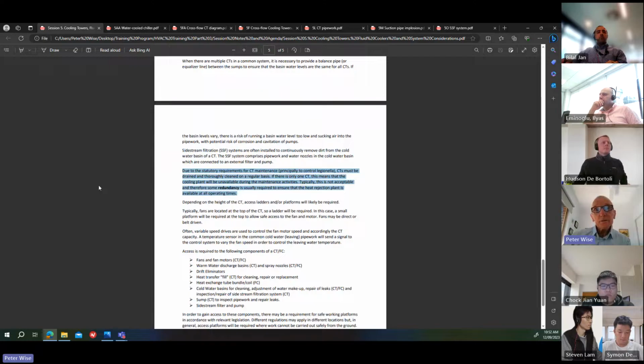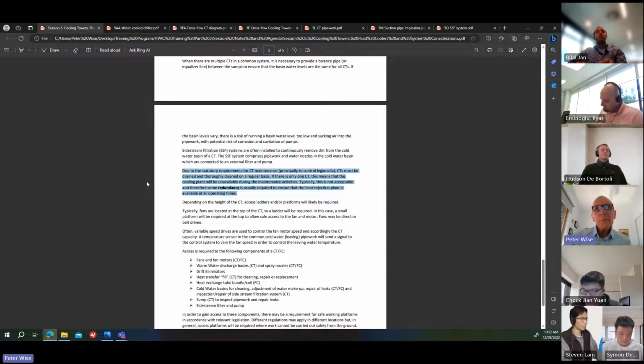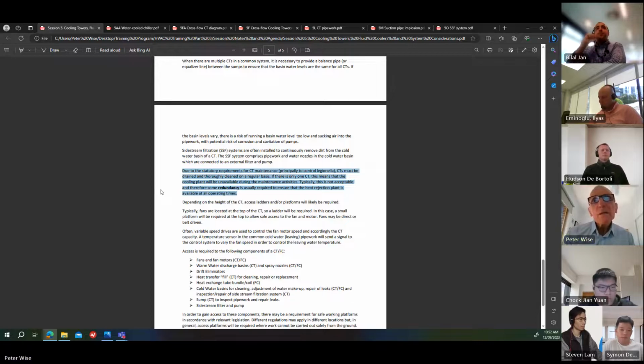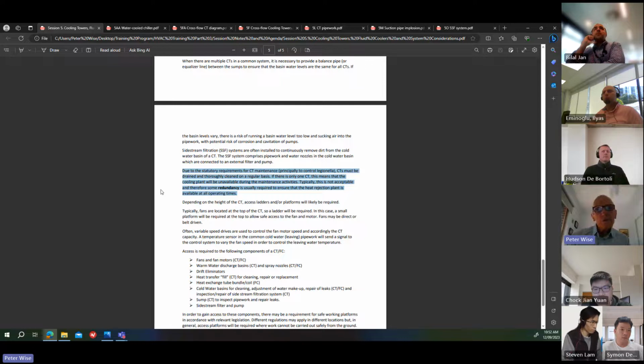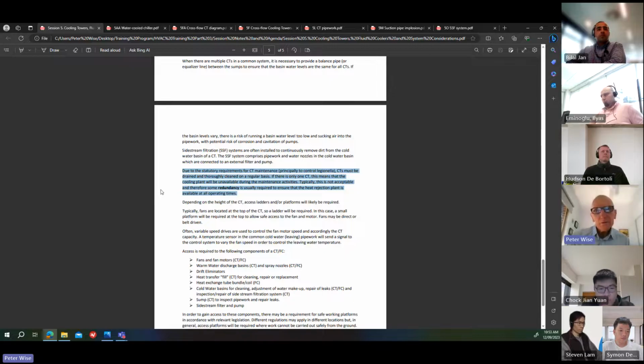Now, there are statutory requirements for cooling tower maintenance. As I mentioned before, a cooling tower has to be registered with the local council, so the council knows it's there and it's got to be looked after. The idea is principally to control Legionella, because nobody wants Legionnaires' disease to occur in their local area. Part of the requirements are that the cooling towers must be drained and thoroughly cleaned on a regular basis. If there's only one cooling tower, this means that the cooling plant will be unavailable during the maintenance activities. Typically, this is not acceptable, and therefore you need some redundancy. So we usually need more than one cooling tower. You'll usually have two cooling towers so that one can be cleaned while the other one is still running.